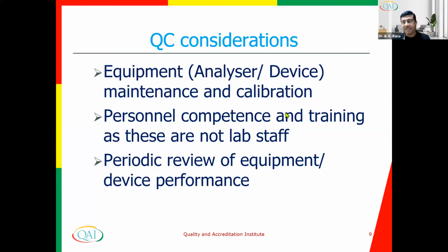And therefore, their competency and appropriate training are required, because compared to a conventional medical lab where people are really trained in handling equipment, their maintenance and calibration is different than there. So the situation is really different, and therefore we really need to put more emphasis on the people who are using these devices or equipment or analyzers for doing the testing. And a periodic review of equipment and devices being used is needed, checking performance against the defined performance criteria. Very simple example, like we use a glucometer. Using the glucometer looks very, very easy, but there are a lot of variations depending on the use and on the maintenance.